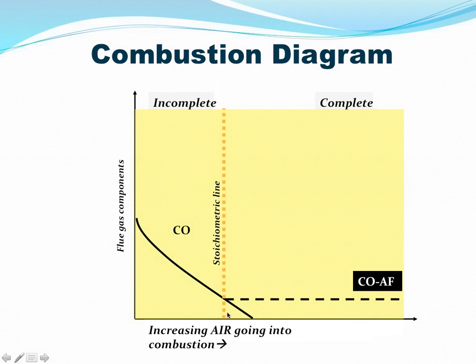The interesting thing to note here is no matter what the excess air situation is, moving to the right, it's going to be the same level of CO air free. And the CO air free number will always be higher than the raw CO reading. Okay, so that's another thing to capture from this graph, is that the CO air free number will always be higher than the raw CO because it's being diluted, the diluted CO reading.